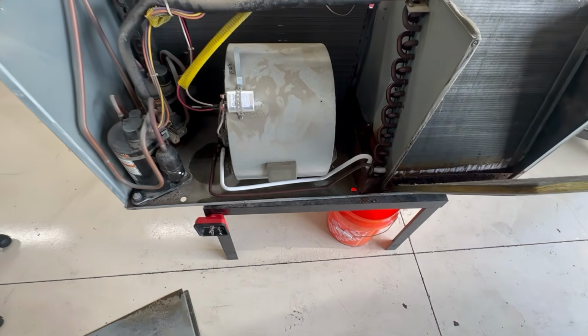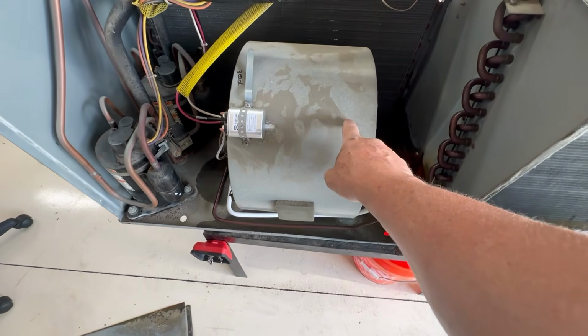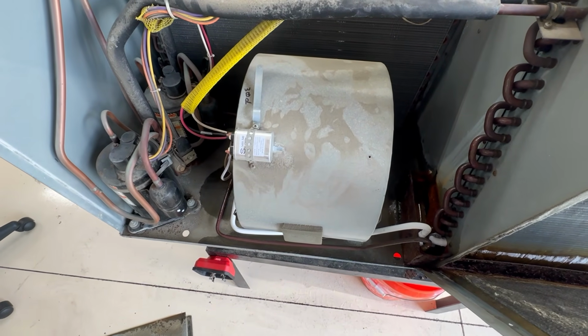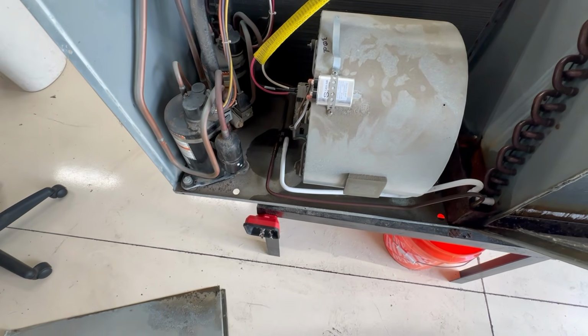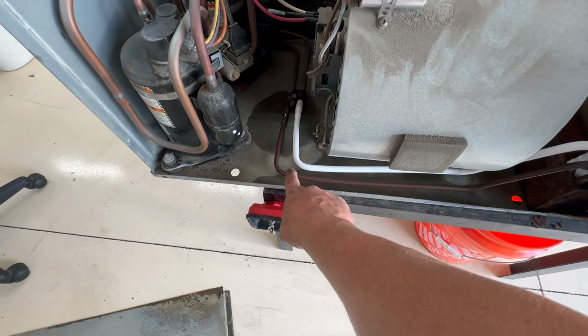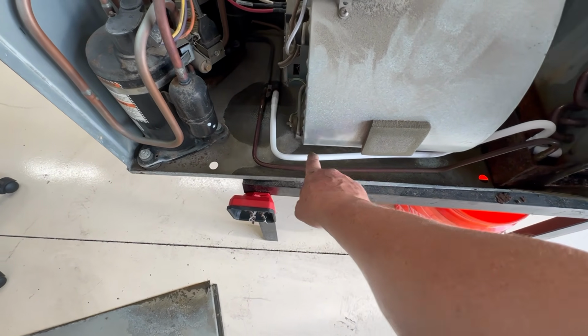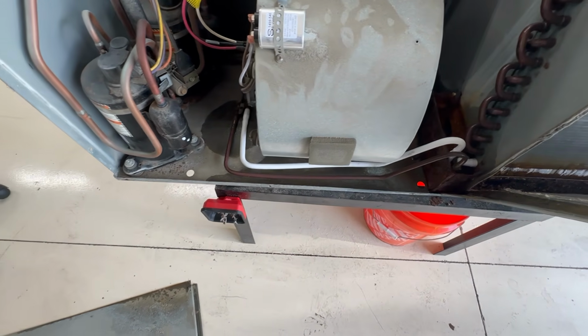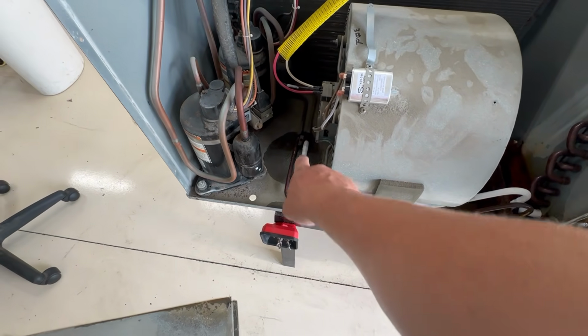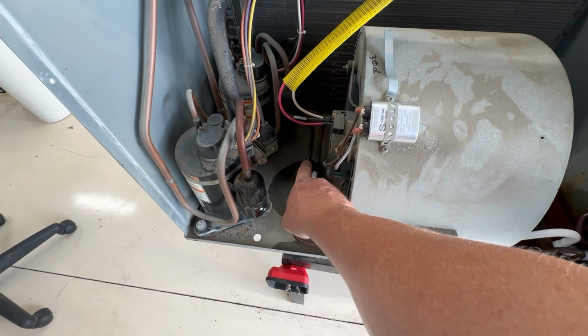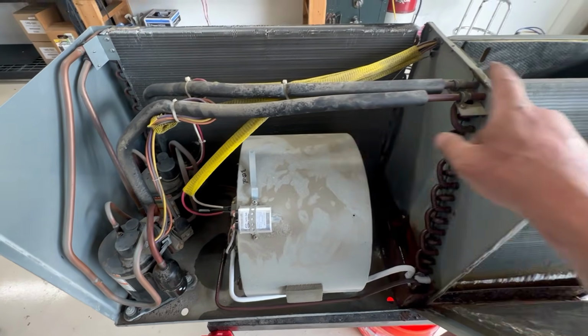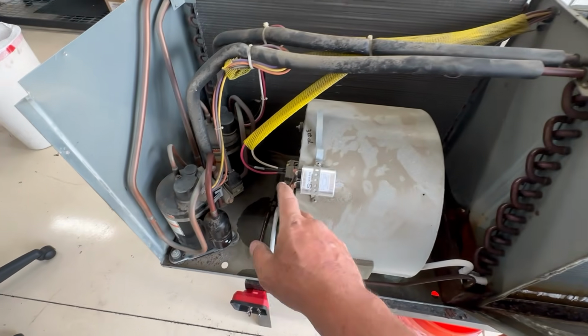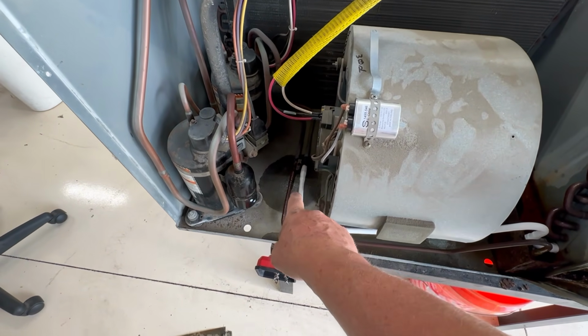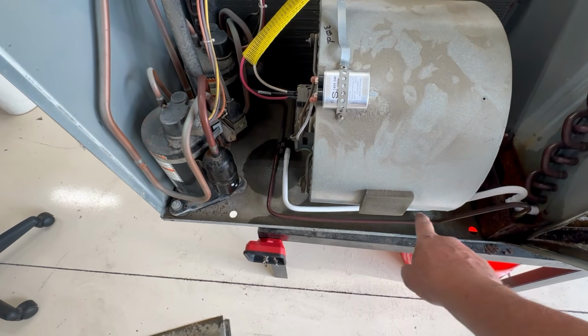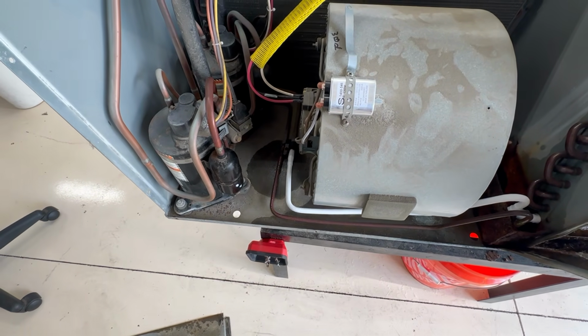Now I want you to look and see how much that fan motor's vibrating. That blade's got a problem. But what I want you to see - this is circuit 1, this is circuit 2. See how circuit 2 has absolutely froze up? So when we go into heat pump mode, those don't equally freeze up, which is normal because coil size obviously is bigger or smaller, it changes the flow. But see how that line, system 2, is absolutely froze up?